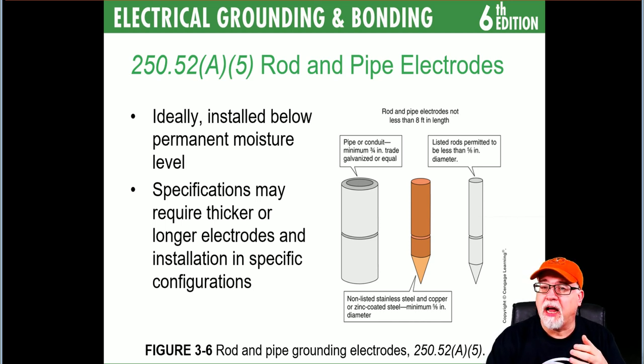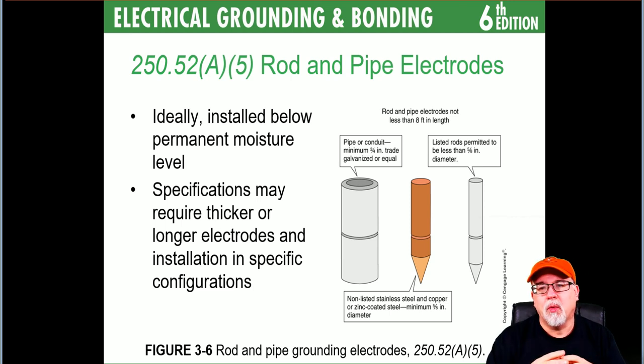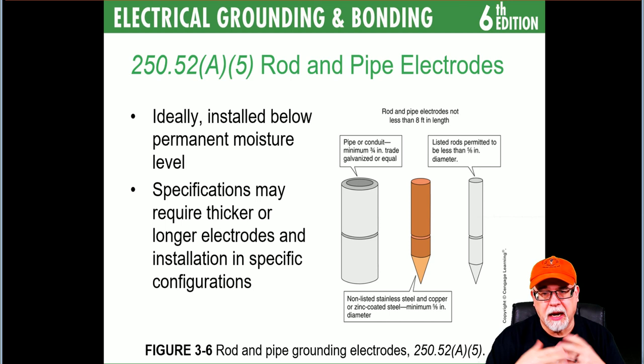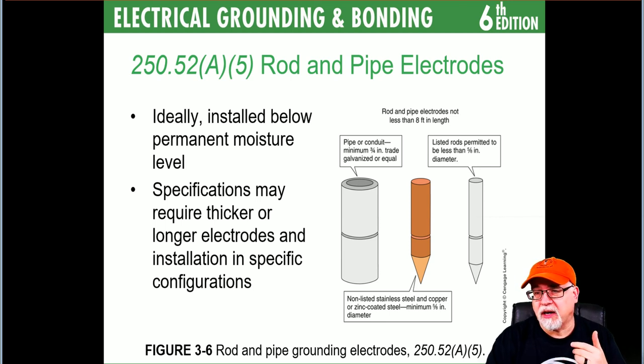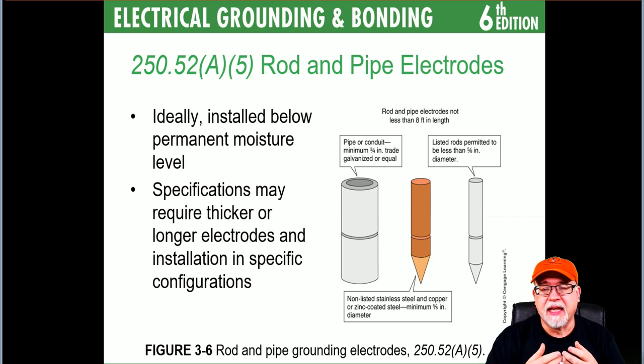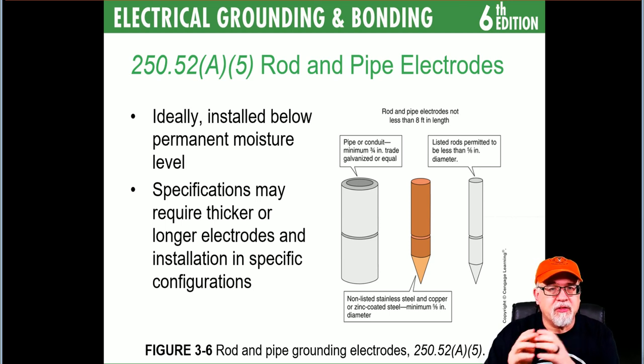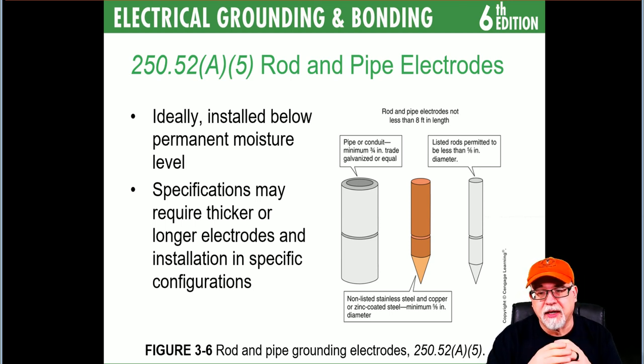250.52(A)(5) deals with rod and pipe electrodes. You can use a pipe or conduit — minimum three-quarter inch, galvanized or equivalent. More often than not, we drive ground rods, which can be copper, zinc-coated steel, or non-listed stainless steel. If you have a listed ground rod, it's permitted to be less than five-eighths of an inch in diameter. For non-listed ground rods, the minimum size is five-eighths of an inch. Listed ground rods have been evaluated — if they have a diameter less than five-eighths yet still got their listing, they're okay.